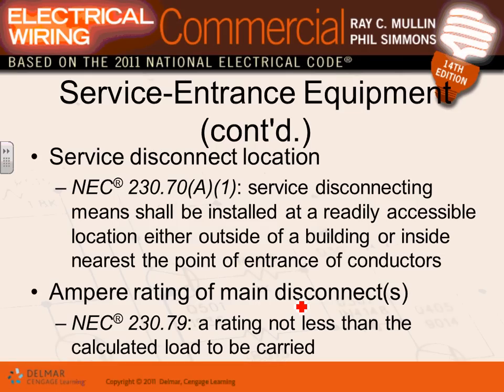Service disconnects. Every service must end up with a disconnect and a fuse. They call this a service disconnect, and they call this a service overcurrent protection device. They're all sized based on the calculation that you do from Article 220, you calculate loads based on Article 220. It has to be readily accessible and in or on the building, inside or outside, as close to entering the building as you can.